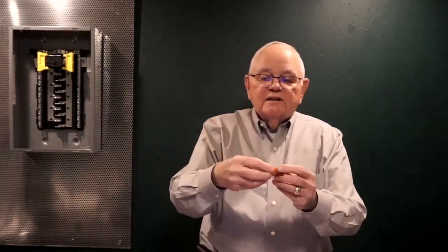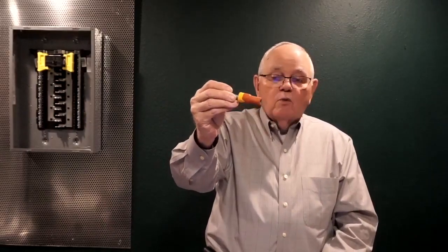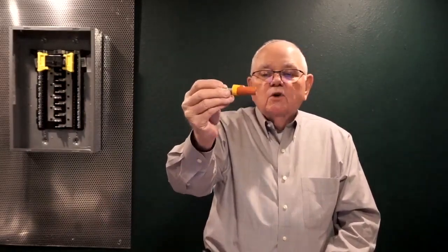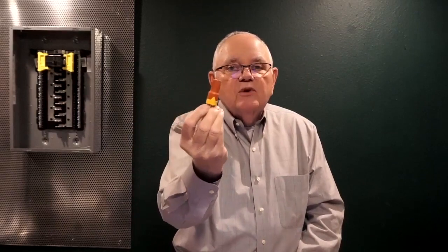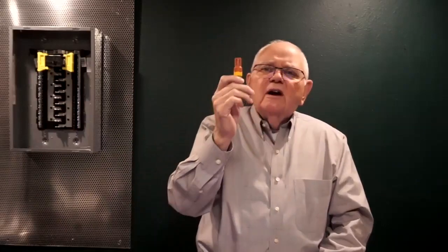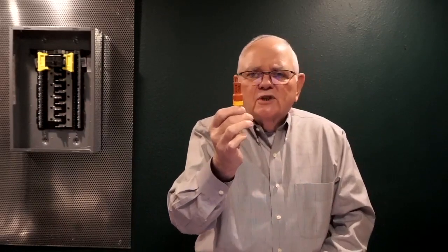Let's talk about this tool a little bit then, our isolated bit holder. We said it's rated for 1,000 volts, just like the screwdriver is. So where can we use it? Well, depending on what I'm doing, I may be able to use this inside the restricted approach boundary, but an important part of understanding that table, and it's in 130.4 on shock protection boundaries, they have one table for alternating current and one for DC. But it tells me in the AC table, if the voltage is up to 120 volts, there is no restricted approach boundary. For the restricted approach boundary at 120 volts, it's avoid contact. So at 120 volts, I just simply avoid contact.